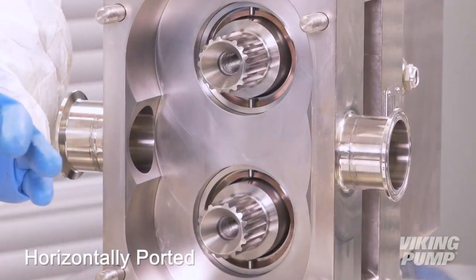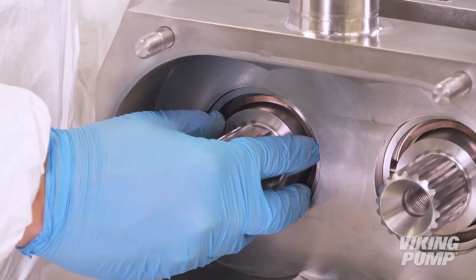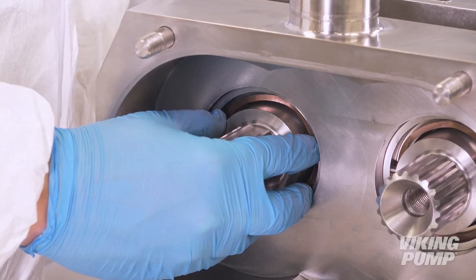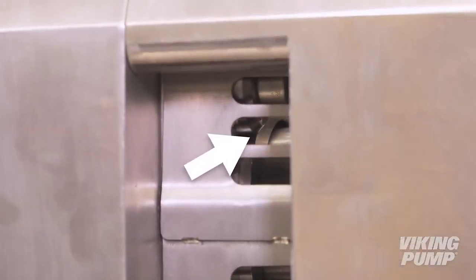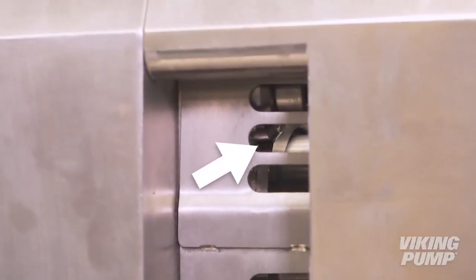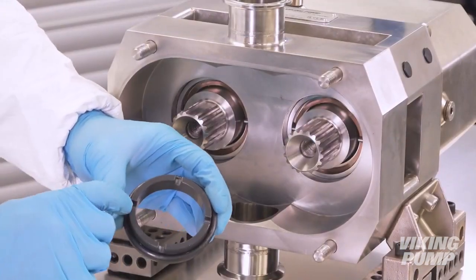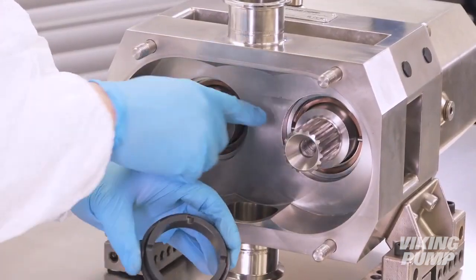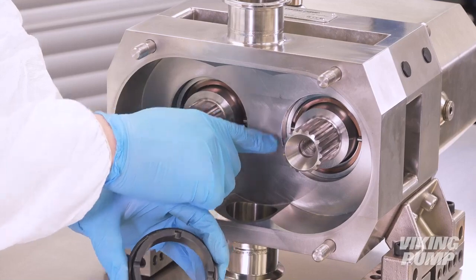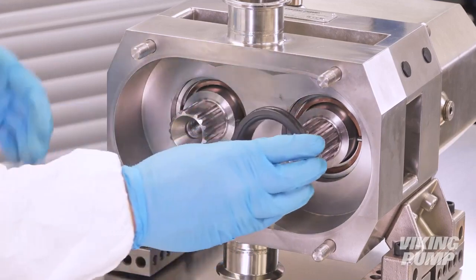In the case of a horizontally ported pump, the pins will be aligned vertically with the shafts. Press in and adjust as necessary until the seal housing is flat at the bottom of the bore and fully engaged with the seal washers. Press each static seal face into the seal housing, making sure to align the slots in the seal face with the anti-rotation pins in the seal housing.